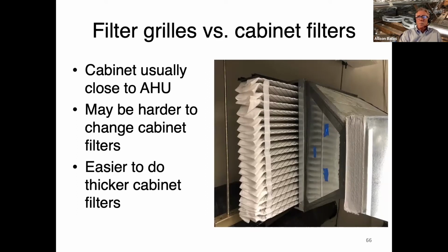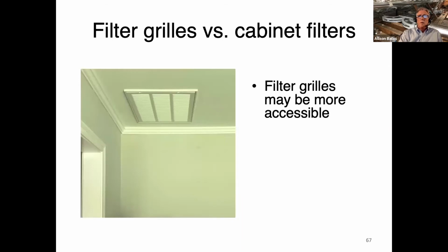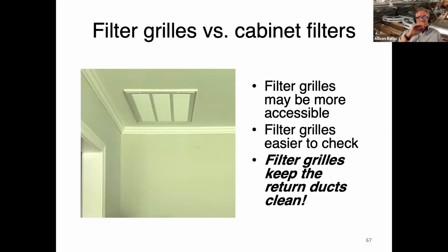One advantage of the cabinet filters, though, is it's easier to get a thicker filter. You can do 4-inch filters on filter grills, but 2-inch filters usually are easier to do for filter grills. Filter grills are in the living space, not in an attic or a crawl space, so they're often easier to get to and check. And they also keep the return ducts clean, because if you put the filter near the air handler, all the ductwork before that filter is running dirty air through it. And dirt will build up in that part of the duct. Is it a big deal? Not really, as long as you get it filtered out before it gets redistributed to the house, but it does build up, and it's better to not let it build up, get that on the filter and just get it all out of the house.